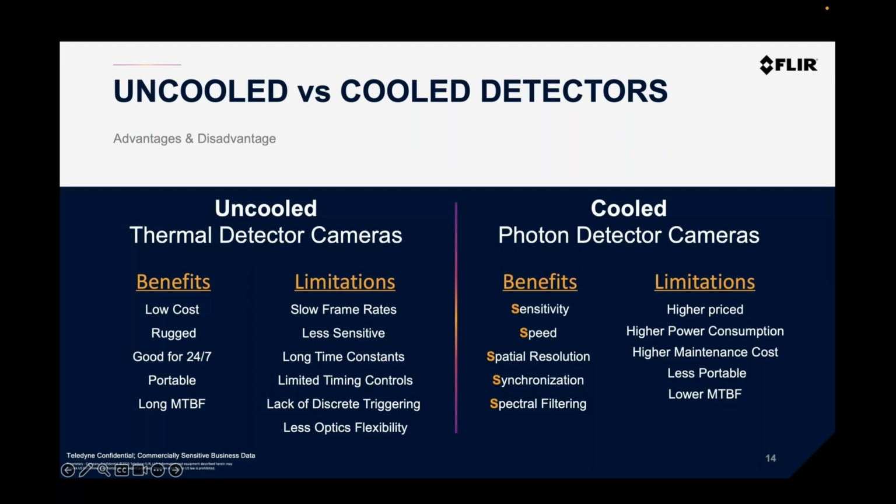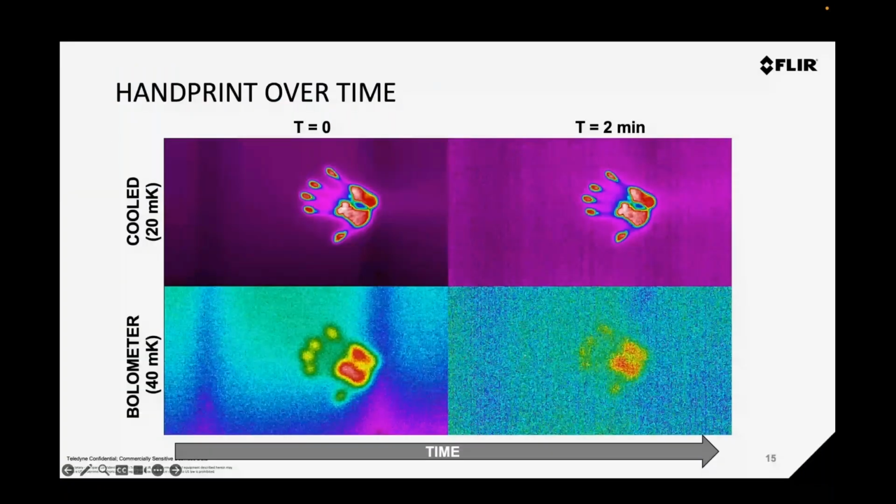The first characteristic is sensitivity. And on this slide is the classic handprint demonstration. If you've ever been introduced to a thermal camera, you've probably seen this handprint demo from someone. For all its practicality, in any setting, it's very easy to do. It's actually exciting. Who knew that just briefly touching a wall could transfer so much heat? But this is where you step back and you remind yourself how little heat you actually transferred from your hand and actually how sensitive all of these cameras are.